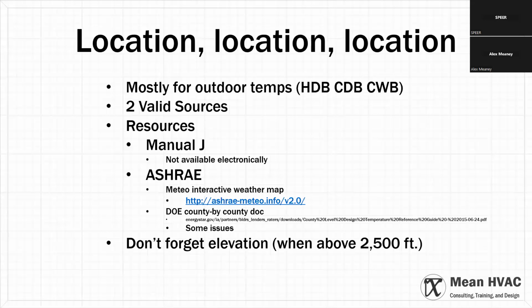I would verify that. But that is occasionally the case at a municipal or a county level, that they'll pass a code, or a state level. I don't think that's happened anywhere but California and Hawaii on a state level, because then I have to break it down for all the places in the state. But on a local level, they will sometimes codify a certain design temperature, and Manual J does allow for that.